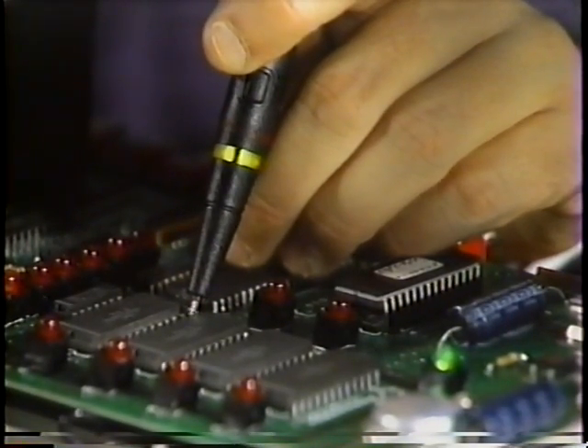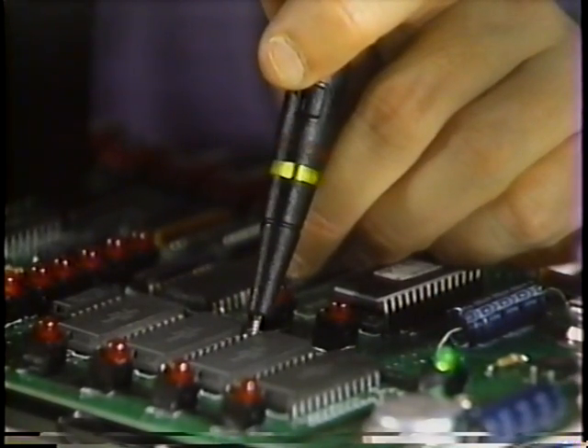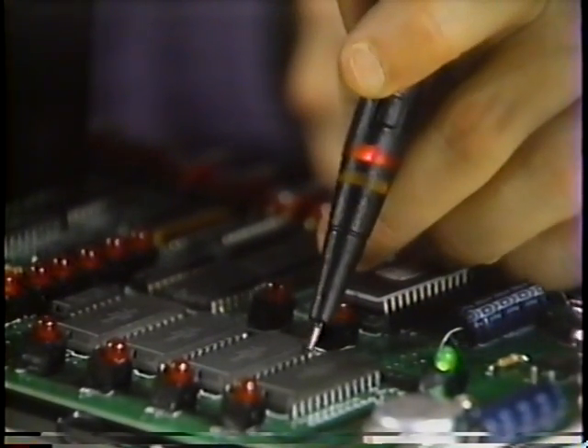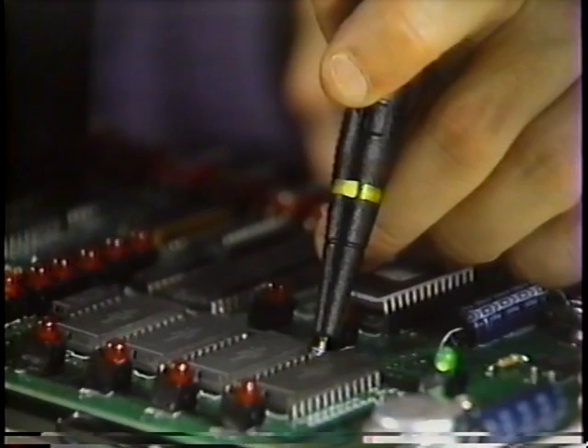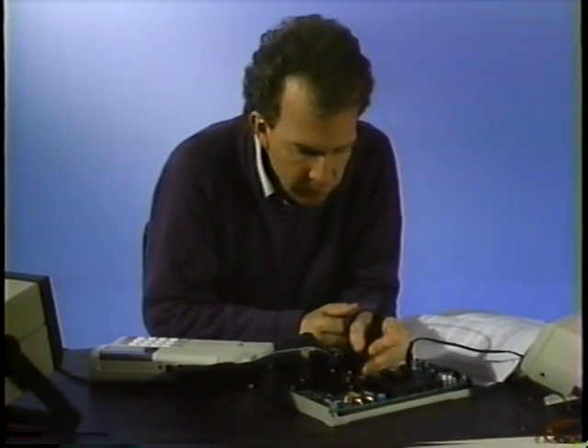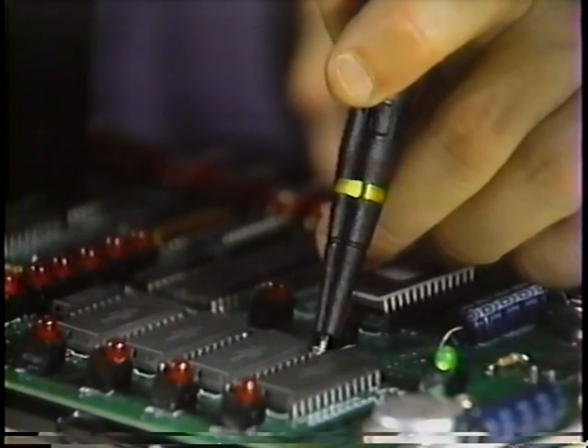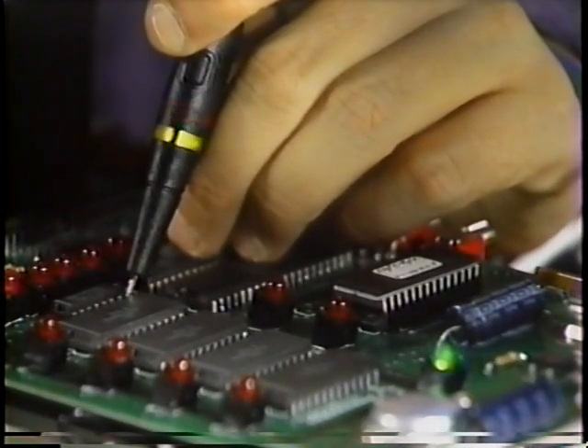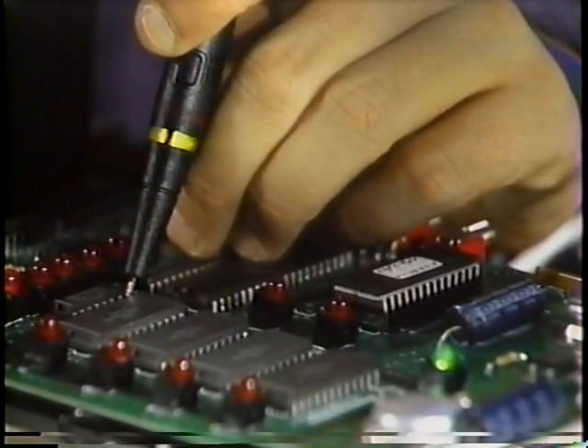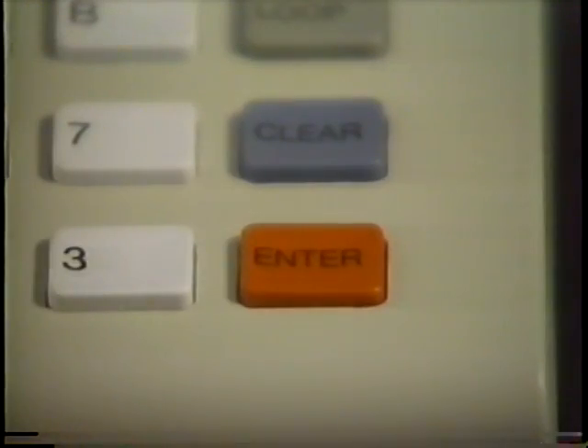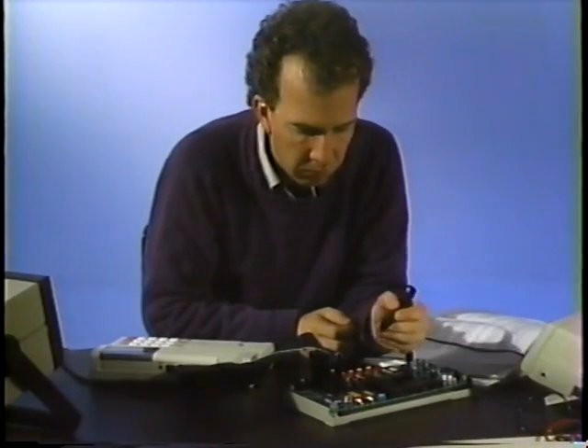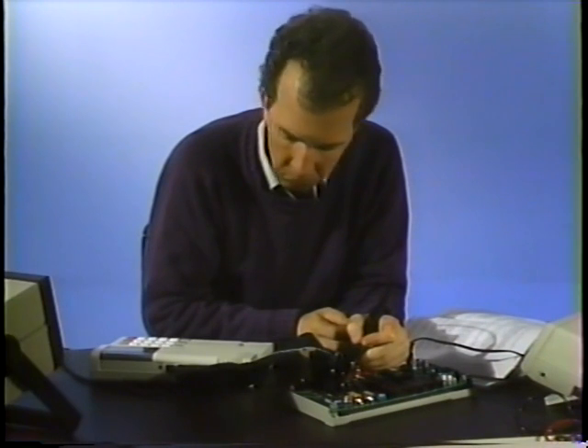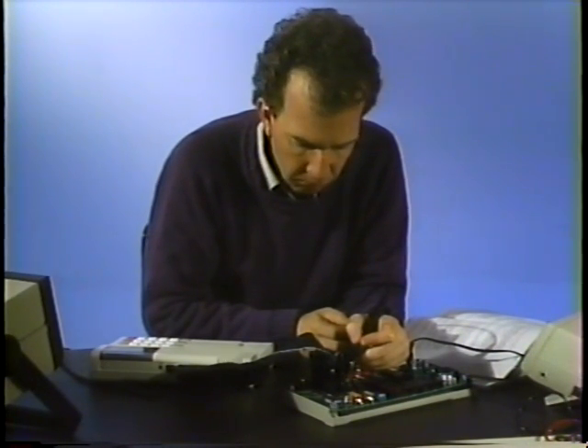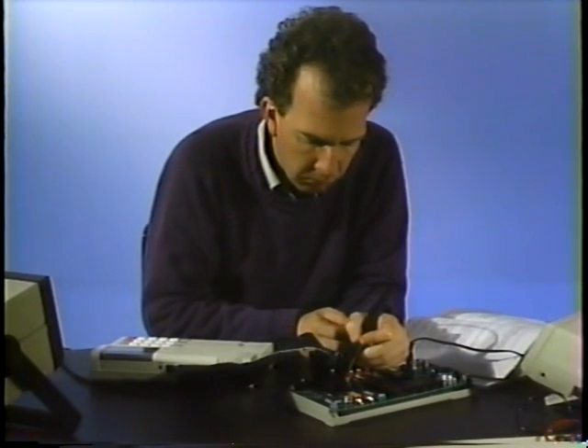In this test, the Fluke 90 exercises the data, address, and control lines and searches for corresponding activity at the probe, so you can trace a suspect bus line through the UUT and identify problems, such as shorts or opens. To execute the test, select Quick Trace and press Enter. Touch the probe to a node on the UUT bus. The probe lights will change from red to green, and the display will indicate the signal line probed.